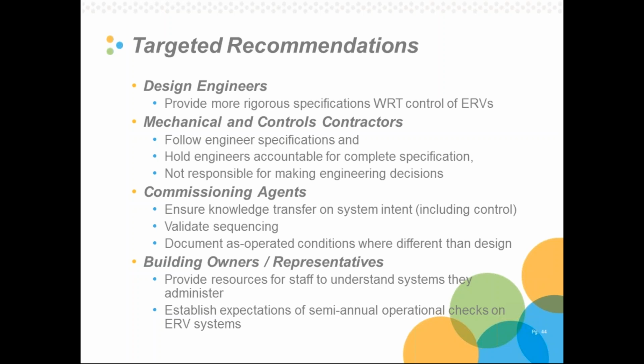Commissioning agents, excuse me, again, should ensure knowledge transfer on system intent, including control, validate the sequencing, document the as-operating conditions compared to design conditions, and communicate expectations to building owners and representatives. And then lastly, building owners. They've got to provide the resources to staff to understand these systems. It's unfair to make operators learn from the systems as they work on them. They should have some idea of an expectation before they administer these systems. And owners should really establish expectations of at least semi-annual operational checks on ERV systems. Again, they're easy to validate, and it's easy to find all the ones that are working. And if we do that, we can focus our attention on the ones that aren't working.